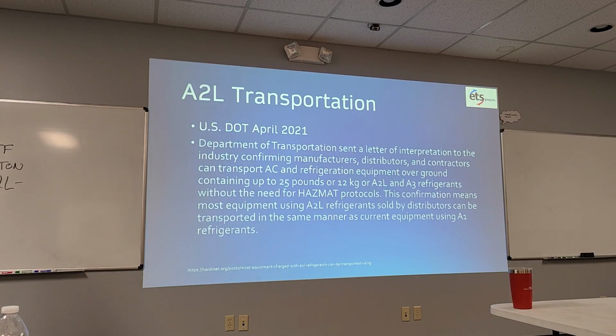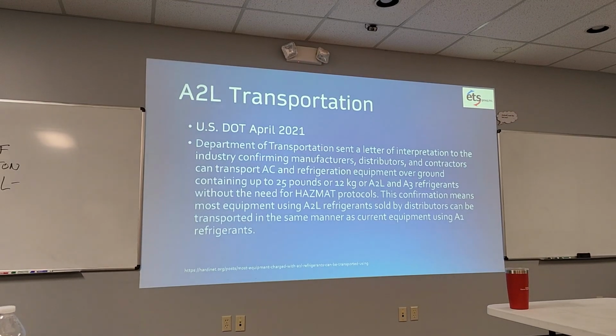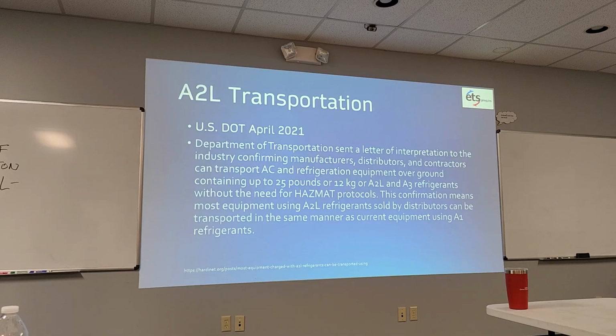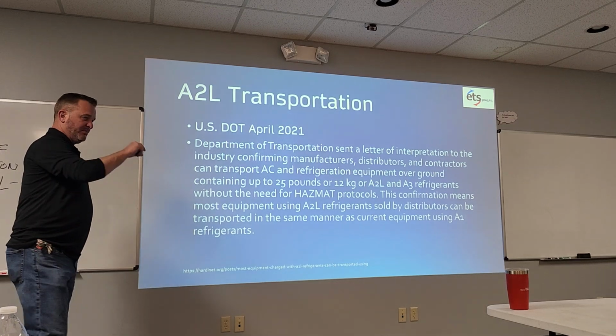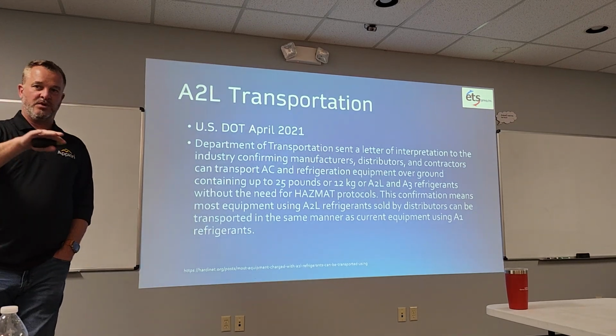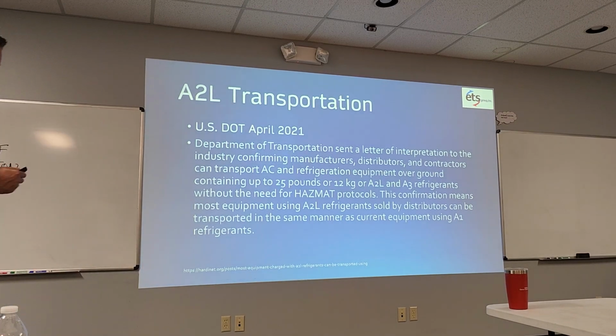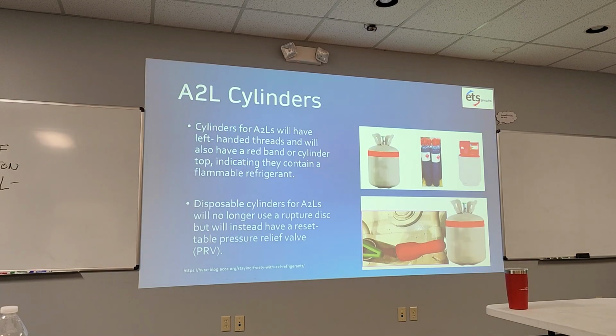Transportation, as far as I know for you guys, as of right now there's no difference transporting A2Ls than 410A, same thing. There is supposedly a requirement that they have to be transported vertically instead of horizontally. I've heard that, and the reason is because of the valves, the rupture discs, the relief valves. So I won't get into all this, but you pretty much follow the same rules as you do with 410. There is one difference between the cylinders, and I'll talk about that now.